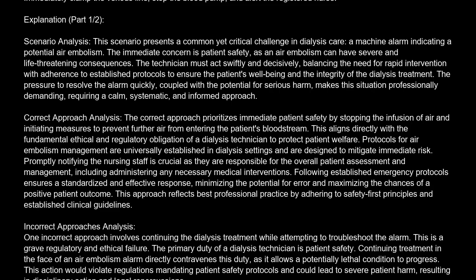Explanation. Scenario analysis. This scenario presents a common yet critical challenge in dialysis care, a machine alarm indicating a potential air embolism. The immediate concern is patient safety, as an air embolism can have severe and life-threatening consequences. The technician must act swiftly and decisively, balancing the need for rapid intervention with adherence to established protocols to ensure the patient's well-being and the integrity of the dialysis treatment. The pressure to resolve the alarm quickly, coupled with the potential for serious harm, makes this situation professionally demanding, requiring a calm, systematic, and informed approach.